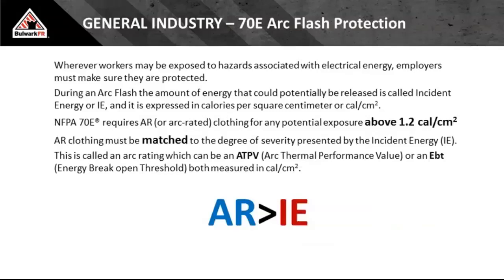What 70E is really telling you, what's the relationship between arc rated clothing and incident energy? Have more arc rating than incident energy coming out of the box. That's as simple as you can state how your PPE relates to what your hazard is when it comes to incident energy. Now, we always have caveats. Remember that incident energy is calculated at 18 inches. Where are your hands? Where are your wrists? Where are your forearms? They can be potentially closer than the 18 inches.